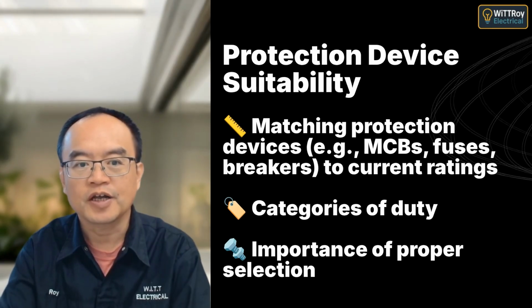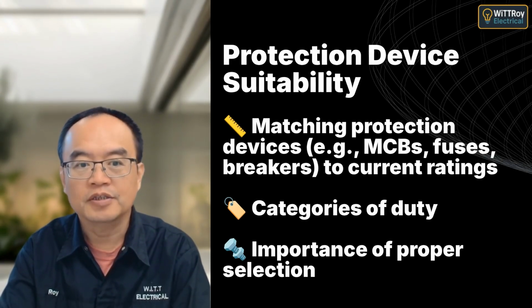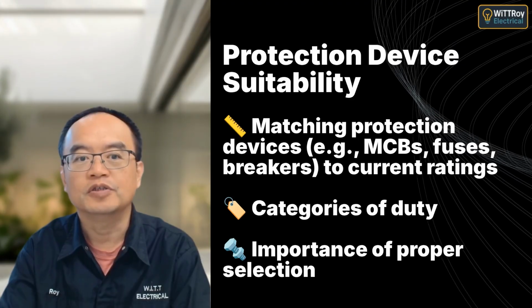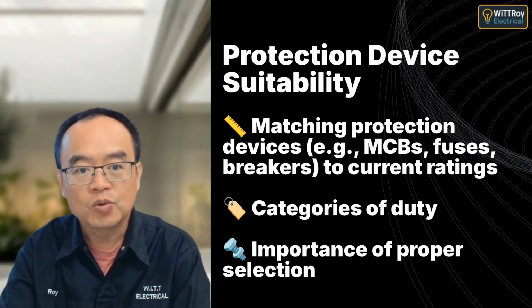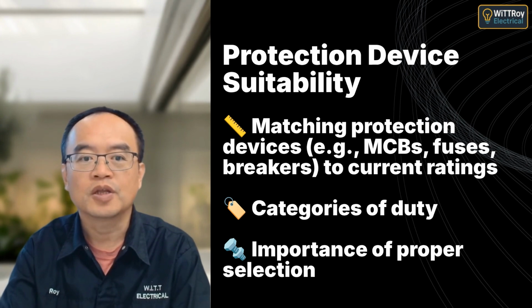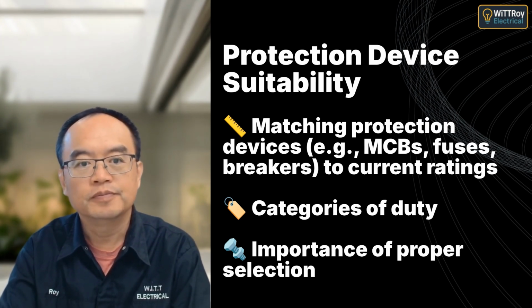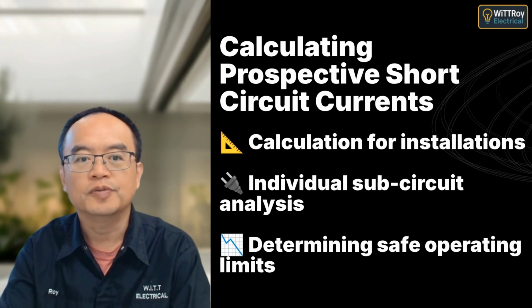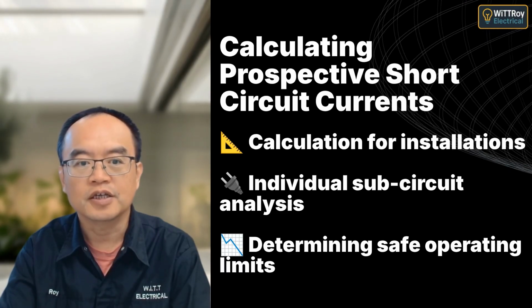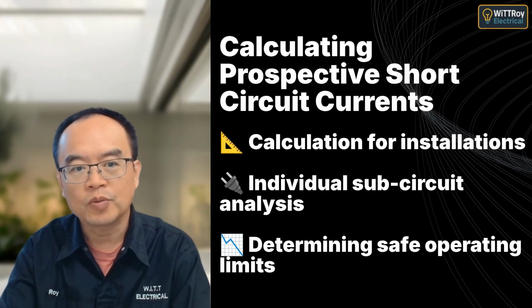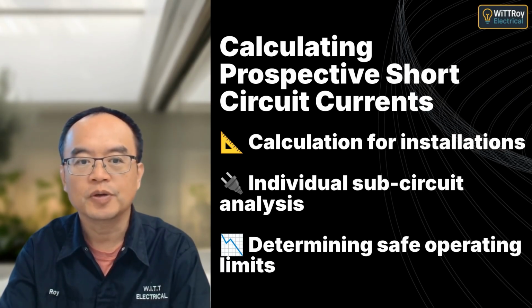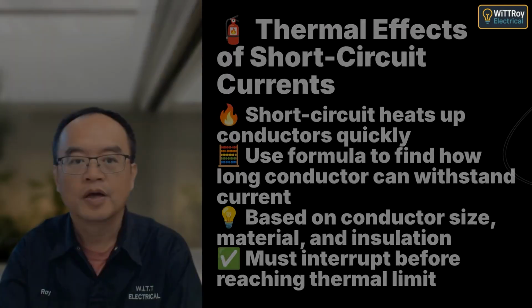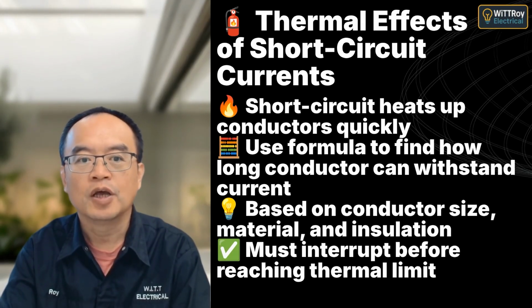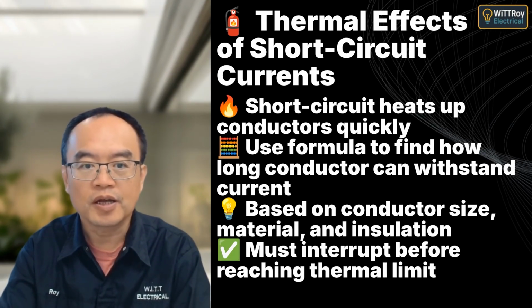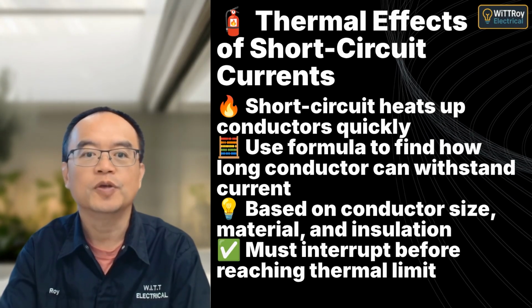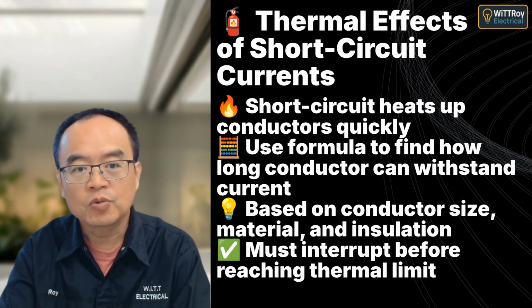Selecting suitable protection devices such as MCBs, fuses, and circuit breakers involves ensuring they are rated for the expected short-circuit current and correct duty category. Proper selection ensures reliable operation, fault clearance, and the safety of the installation. Accurate calculation of prospective short-circuit currents is essential for installations and individual circuits. This ensures equipment ratings are appropriate, preventing failures and promoting safety. A short circuit heats up conductors fast. We use a formula to work out how long the cable can handle that fault. It depends on the cable size, material, and insulation. The breaker must trip before it reaches the thermal limit.